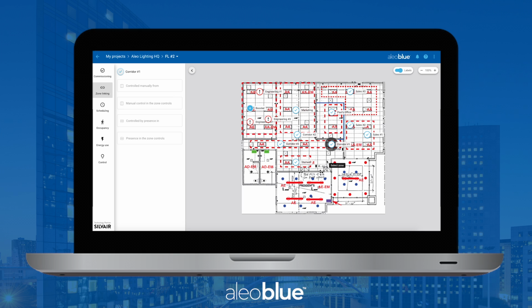After clicking the first zone, you'll see a dark gray circle appear around it. Now click the desired option on the left side, which will bring up a drop-down menu populated by the zones that have been set up. In this example, we're going to select Presence in the control zones and set it to Corridor 2. As you hover over the options, you'll see a light gray circle appear around it. Once selected, the zone will appear in the box, and now they're linked.